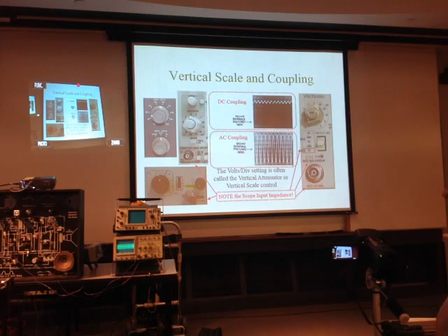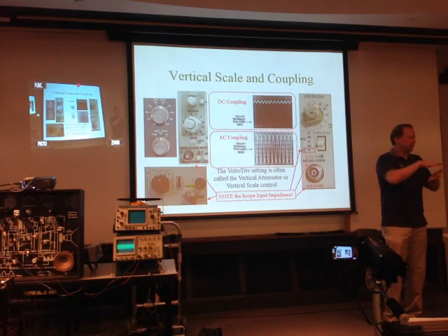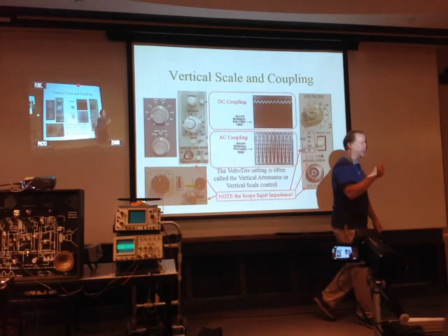The reason I want to say note the input impedance is that later on when we talk about probes, the probes can be adjusted to compensate them to match the frequency response of the scope. And the probes themselves will have a range of input capacitance that they can compensate over. So if you get a probe that can only compensate from 10 to 20 picofarads, and I've got this scope that's got a 25 picofarad input, it won't be able to be properly adjusted to use with that scope. We'll cover that in a little bit.